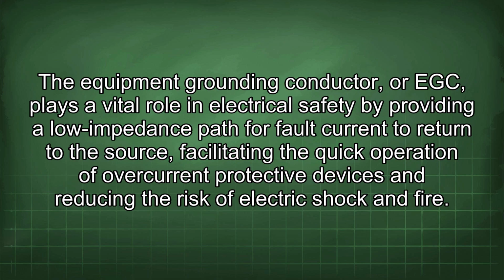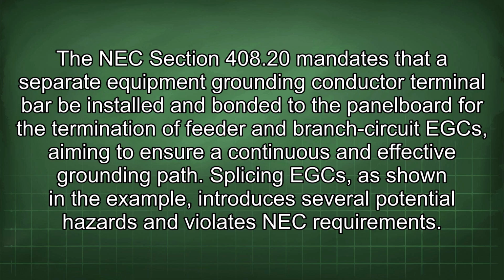The equipment grounding conductor, or EGC, plays a vital role in electrical safety by providing a low impedance path for fault current to return to the source, facilitating the quick operation of overcurrent protective devices and reducing the risk of electric shock and fire. The NEC Section 408.20 mandates that a separate equipment grounding conductor terminal bar be installed and bonded to the panel board for the termination of feeder and branch circuit EGC, aiming to ensure a continuous and effective grounding path.